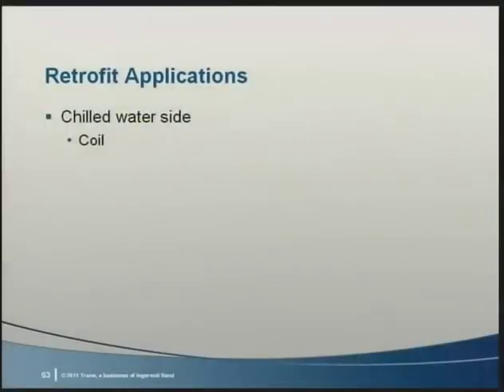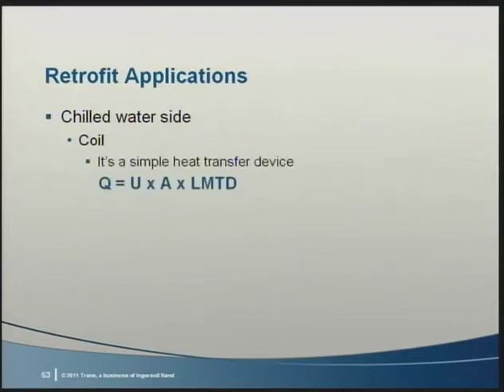First, let's look at how this affects the chilled water side of the system. The amount of heat transferred from a cooling coil is dependent on the equation U times A times LMTD. As Don Appelheimer used to say, everyone remembers what LMTD stands for: lovely, magical temperature device. That's what a coil is. And its log mean temperature difference is an asset that can be exploited.